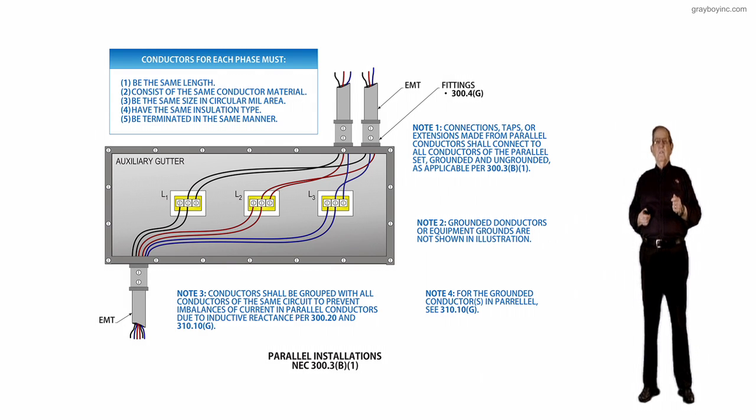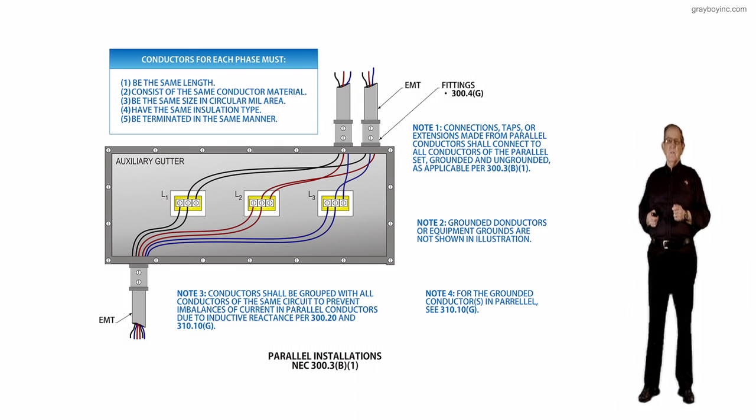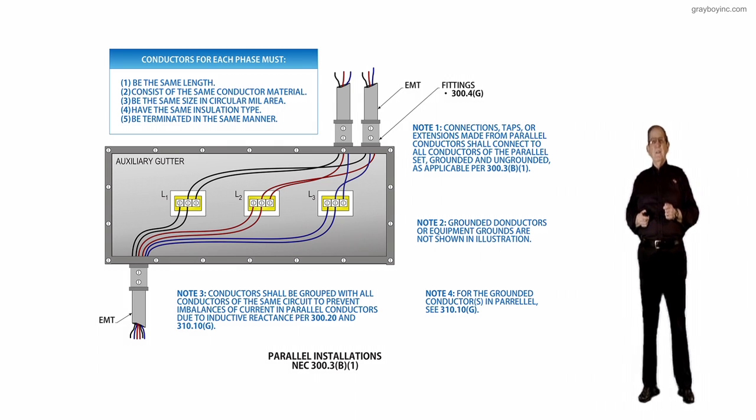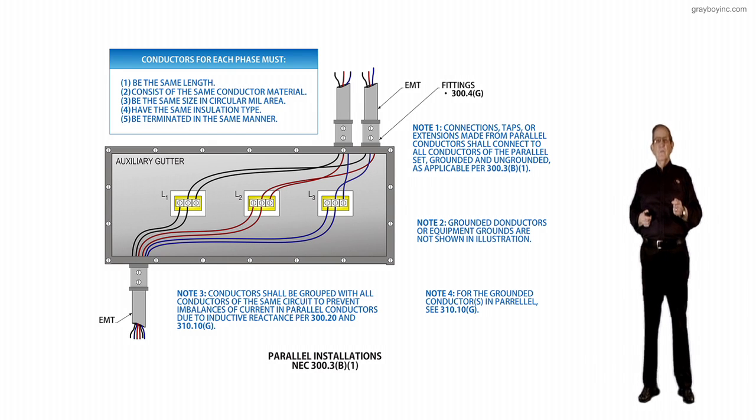Note three states that conductors shall be grouped with all conductors of the same circuit to prevent imbalances of current in parallel conductors due to inductive reactance per 300.20 and 310.10G. We have to follow note three for a particular group.